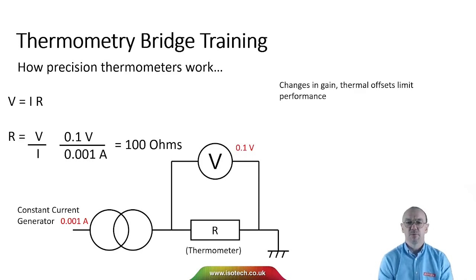So with a precision thermometer, very simplistically, they work by passing a known constant current through the platinum wire. And then we measure the voltage, and from measuring the voltage we can determine the resistance, and from the resistance, temperature. And the limitation of this type of design is if there are changes in the gain and the amplifier, if there are any thermal offsets, as things change it compromises the performance. And with a precision thermometer at best we might get an accuracy of a few parts per million. So good, but not good enough if we want to make the very best measurements we can.